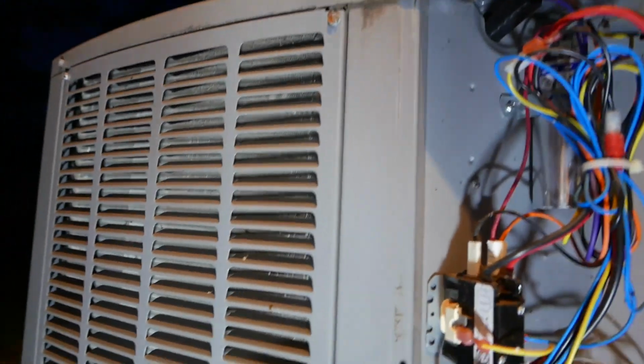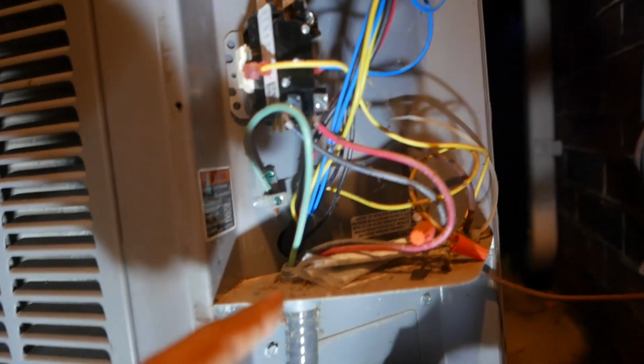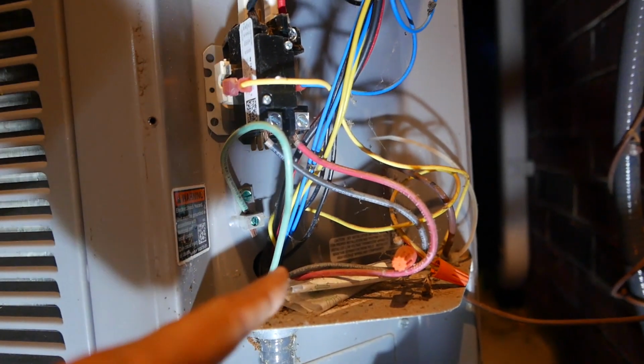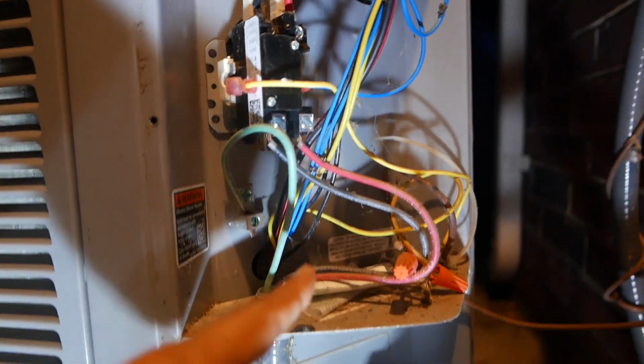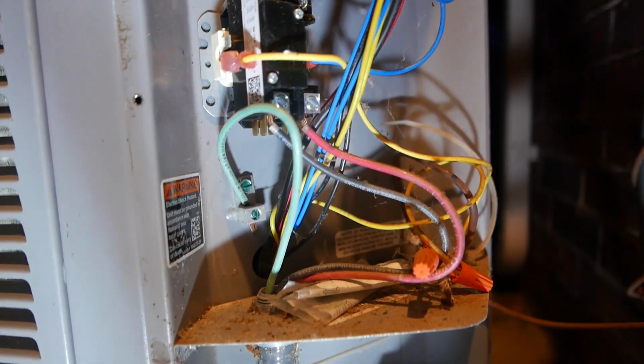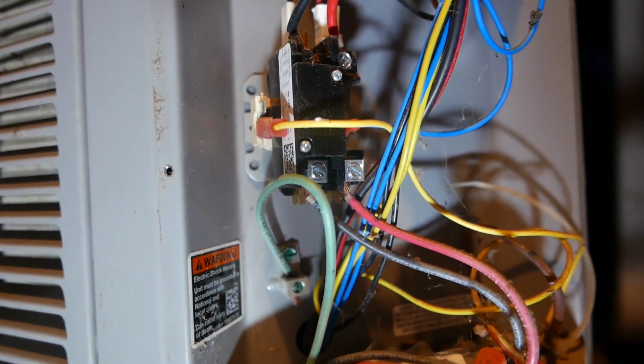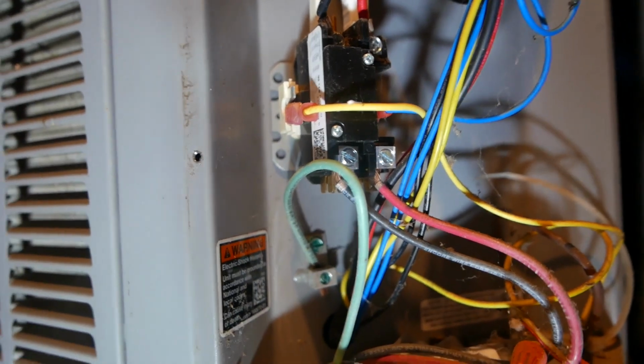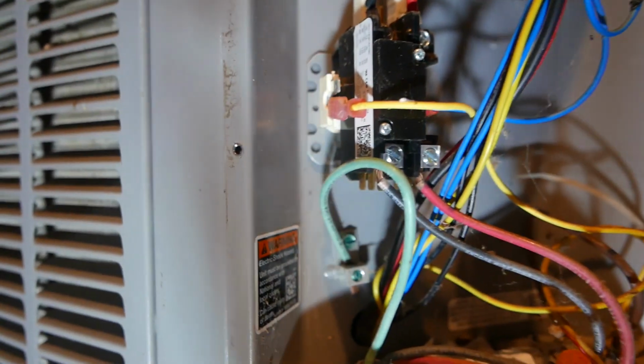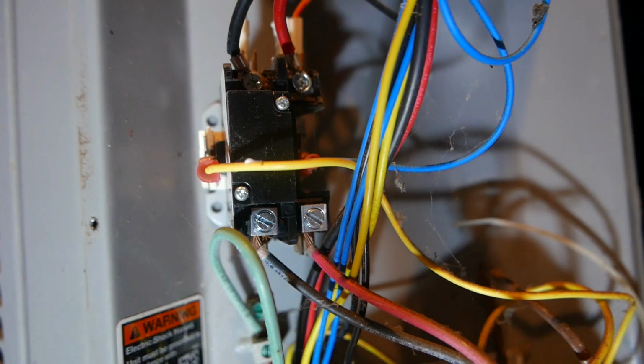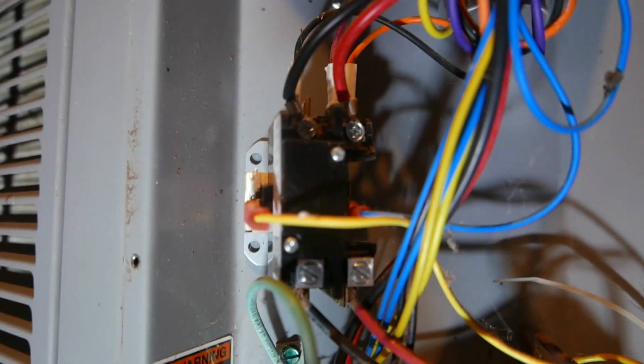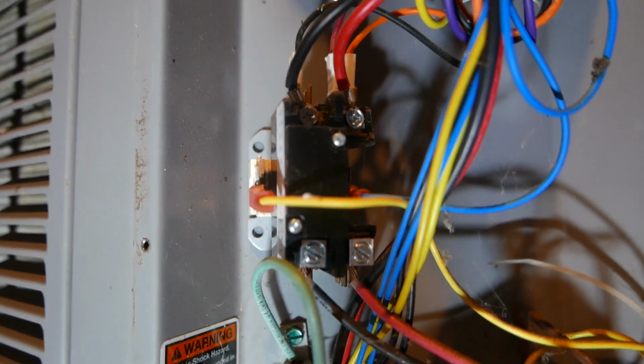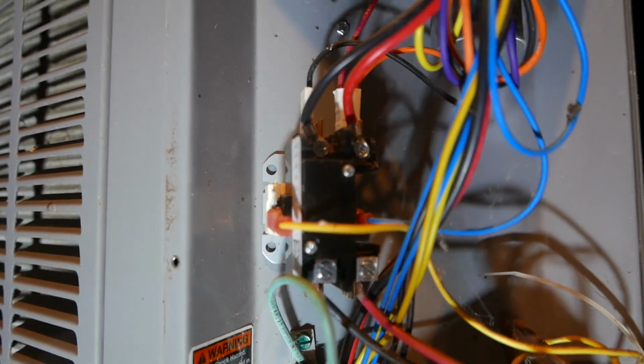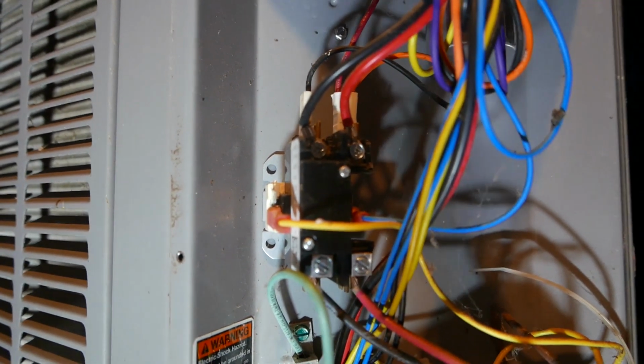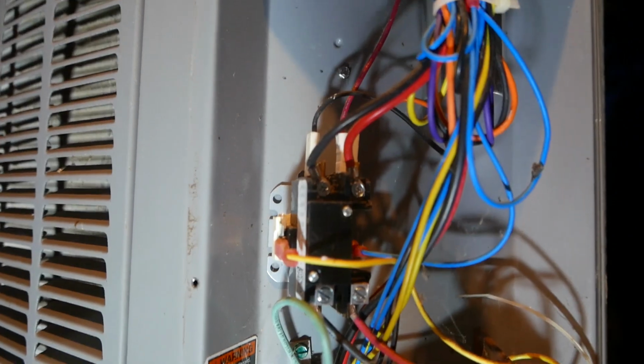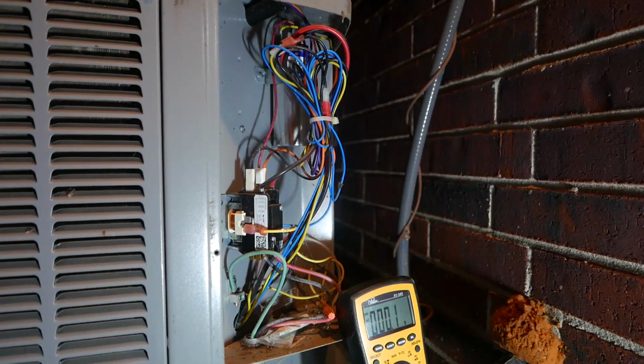So as you can see, the green wire, brown wire, and red wire, 240 volts coming up, and the green wire is the ground, which is tied to the unit right there, but then the brown and the red is going into this black contactor, this black relay. So let's see if there's any voltage that's coming into the unit real quick.